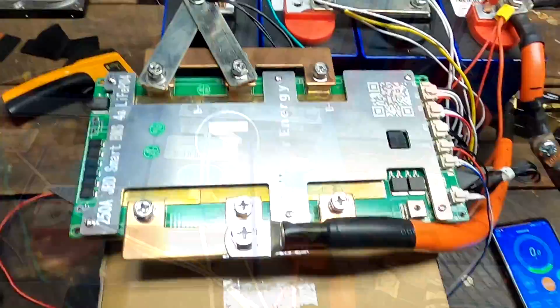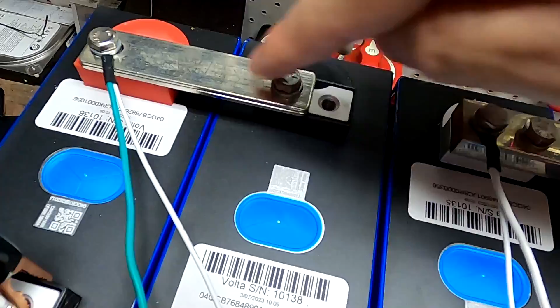So guys, this is now attempt number 3 to discharge this battery here correctly. And I have found there was a resistance between the terminal of the battery cell and the bus bar. And only by using 2 screws and torquing them down to 6 Newton meter each on both sides, I could actually overcome this resistance. I couldn't find anything wrong on the aluminium terminal of the battery. It's the same as on the other ones as well, but I could not get it right.